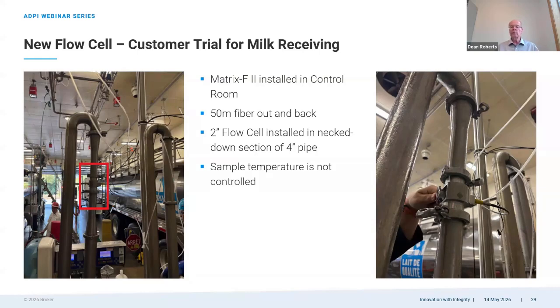But the Matrix F2 is the process instrument. It was put into the control room where we had stabilized temperature for the spectrometer. We had 50 meters of fiber out, 50 meters back, and we put it in a neck down section of a 4-inch pipe. The sample temperature is not controlled because this is the milk tanker unloading. Next slide.